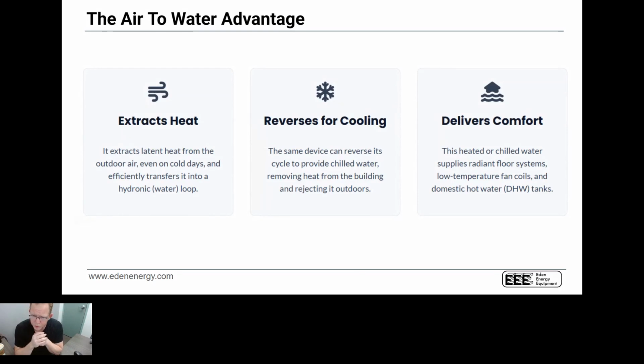What is really interesting, though, is that air-to-water heat pumps are typically a monoblock design, which means that it's a basic water-glycol connection from the outdoor unit to whatever configuration you might have as an indoor unit. It could be prepackaged. It could be something you've put together with the help of your wholesaler and a local engineer designer. But air-to-water heat pumps have some very, very distinct advantages, and most importantly is their ability to do heating, cooling, and hot water.